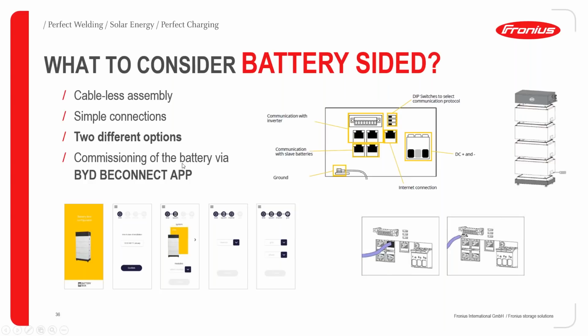Basically there are 4 steps: tell the BCU whether it's an HVS or HVM battery, how many modules you have, what inverter type, and if it's a Fronius inverter always choose on-grid at the end, and of course the phase - in our case with the Symo Gen 24 Plus, a 3-phase device.